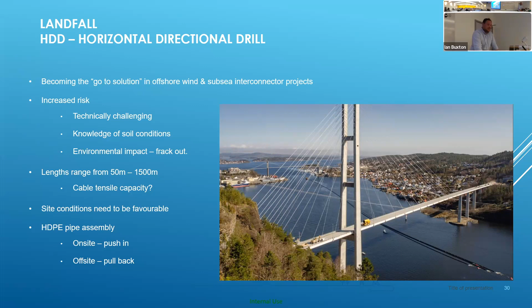Unless you have good geotechnical data, it's very tricky to commit to an HDD without knowing the conditions. HDD lengths can range from 50 to 1500 meters, which really impacts how much tensile capacity the cable can withstand. Site conditions need to be favourable for the HDPE pipe. This is the HDPE pipe used for one project, being towed from Norway, 1.2 kilometres long, with four of them being towed by a tug all the way down to the east coast, which is a feat on its own.